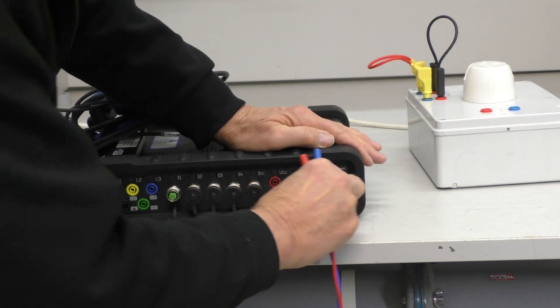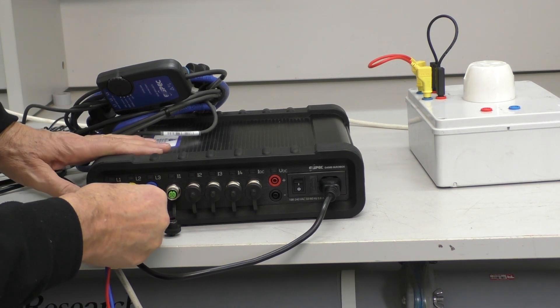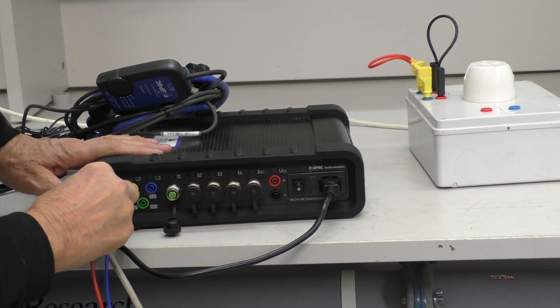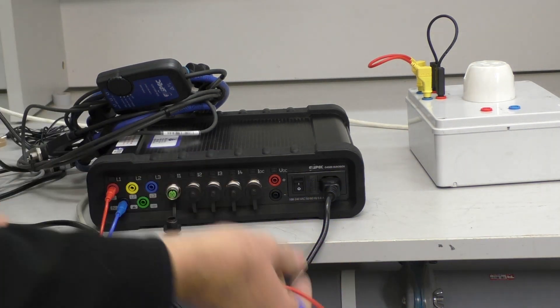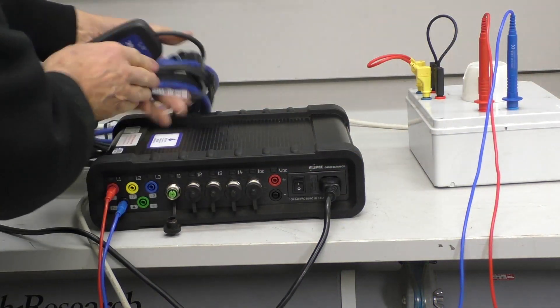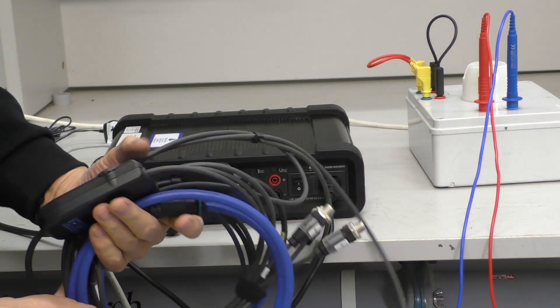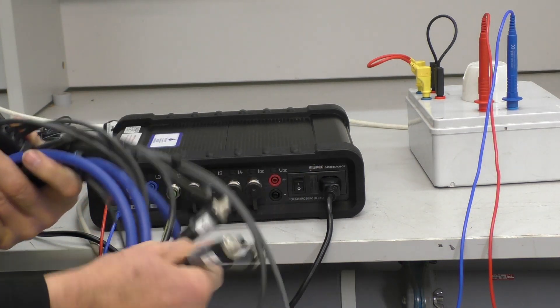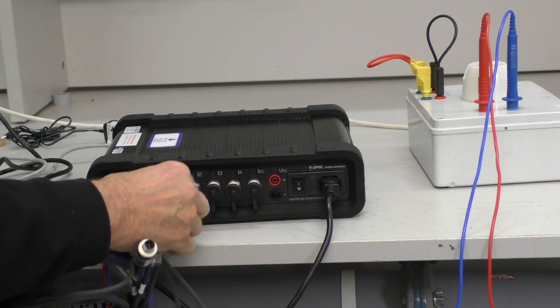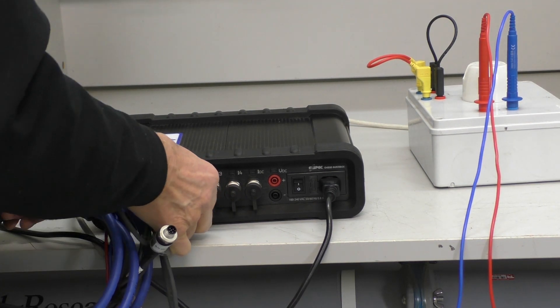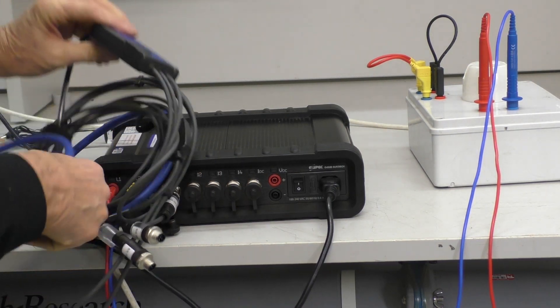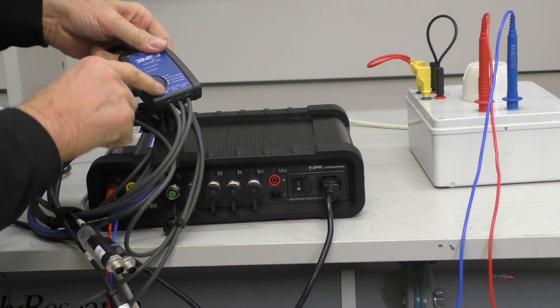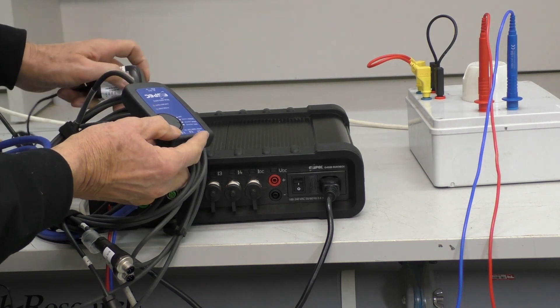Okay, here's the power connector so I'm going to connect power, I'm not going to turn it on yet. We're doing a single phase measurement in this case so I'm going to connect between neutral and the L1 and the other ends of these of course I'll plug into my measurement system. Now we need to connect the clamps up. The clamps are wired as a set of three, in this case I'm going to wire L1 because it's a single phase so I simply plug that in and screw this thing in place. And also we should provide power to this because the battery in this only lasts a short period of time so there is a separate power supply to power this.